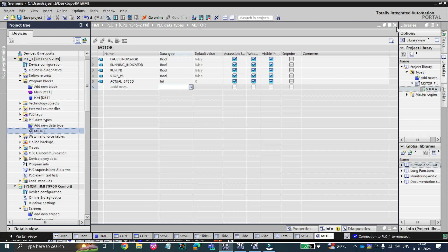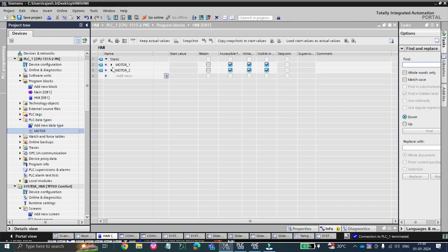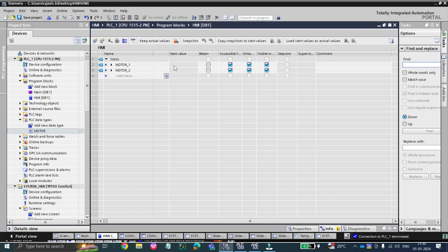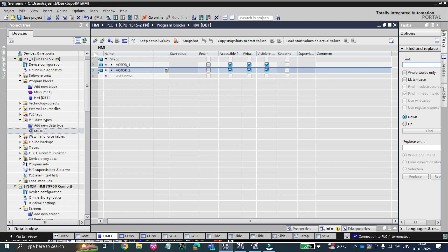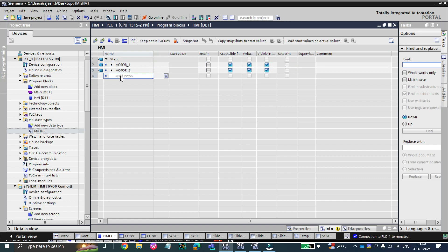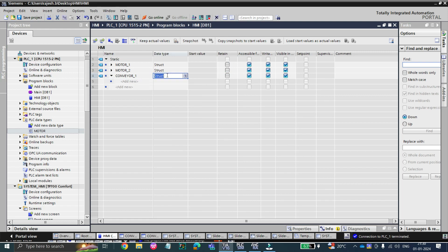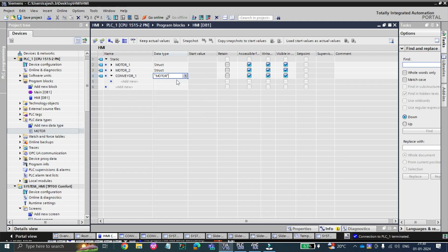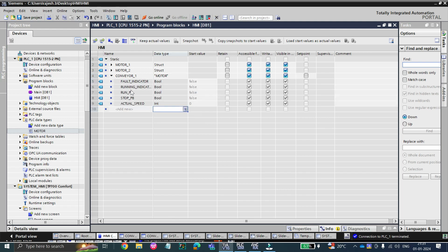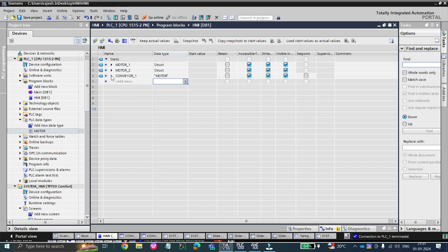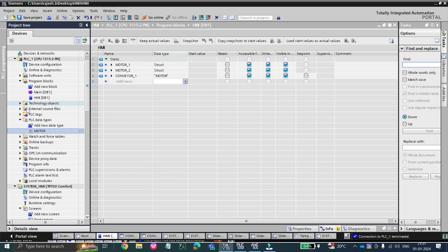Now instead of motor 1, we will delete both the old tags. Let's say we create 'conveyor 1' and set its data type — instead of struct, the data type will be 'motor', which we just created. By expanding it, you can see fault indicator, running indicator, run push button, stop push button, and actual speed — all the elements are now present. But this is still local; to use the motor data type in our faceplate, we need to make it global.